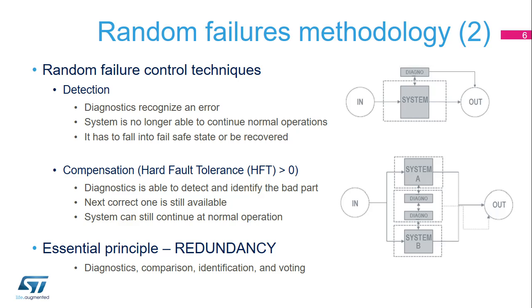Compensation methods usually allow the system to continue operating normally while using error correction, passivation, or masking functions. Generally, a voting process is used to identify the damaged part or incorrect data, which is then replaced by the correct one. Standards recognize hard-fault tolerance, or HFT, as the maximum number of errors which a system can absorb while it can still continue at normal operation. In addition to specific functional testing, redundancy is the essential diagnostic principle here. Both detection and compensation techniques always require a sure level of redundancy to be efficient.